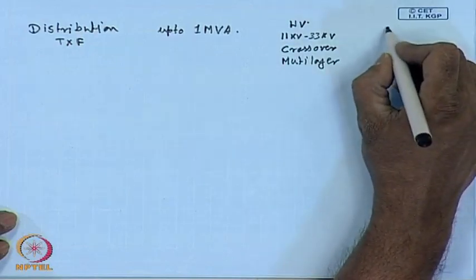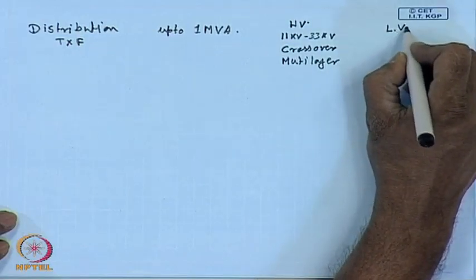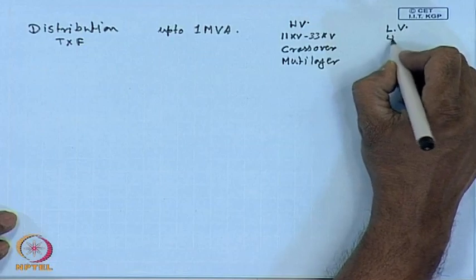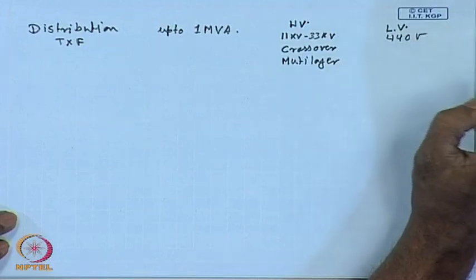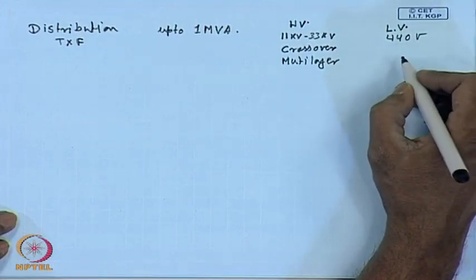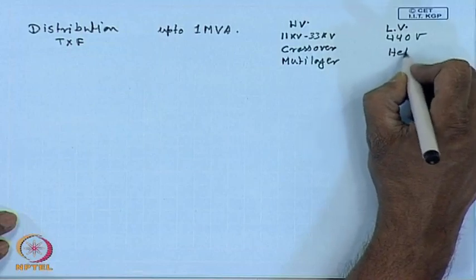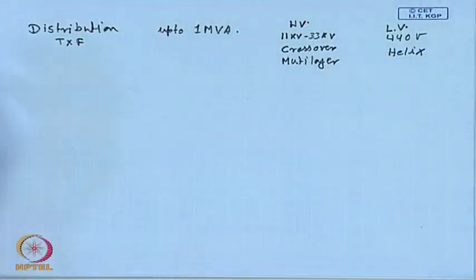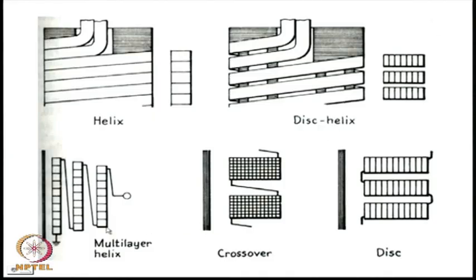Similarly, the LV winding for a distribution transformer will usually be rated at 440 volt. The choice of winding for this is helix, which is shown here. This is the helix winding. This is on the lower spectrum.